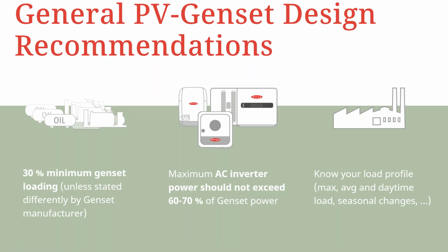So, rounding up with recommendations: like earlier said, please ensure that you have 30% minimum genset loading unless stated otherwise by the genset manufacturer. To complement this, ensure that the maximum AC inverter power does not exceed 70%, or is slightly lower than that. And it is important for the client or the installer to know the load profile of the system, to react to changing load requirements in the system as time goes on.